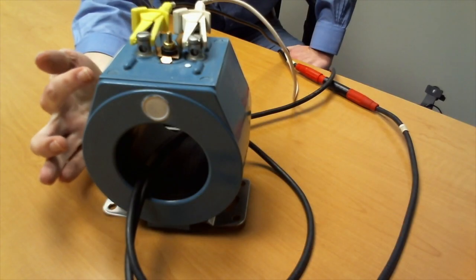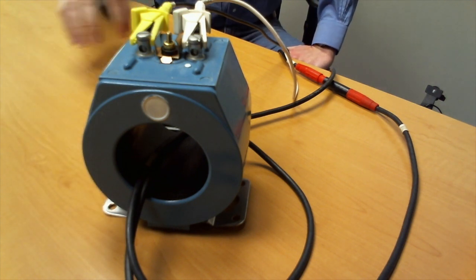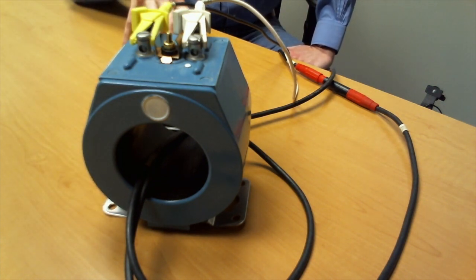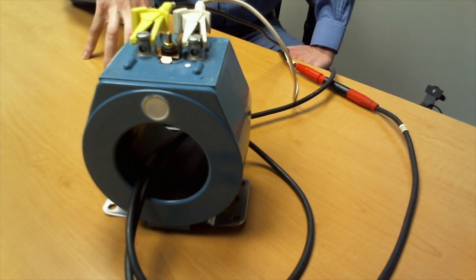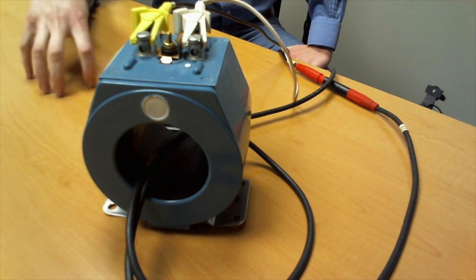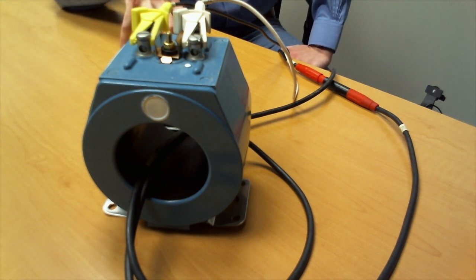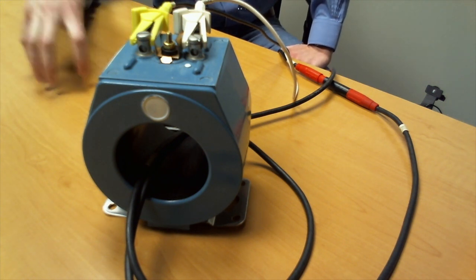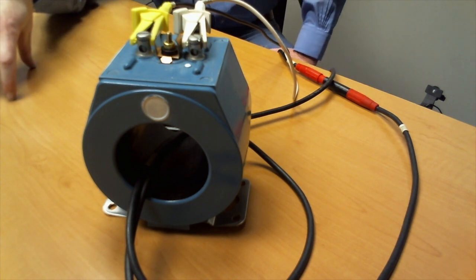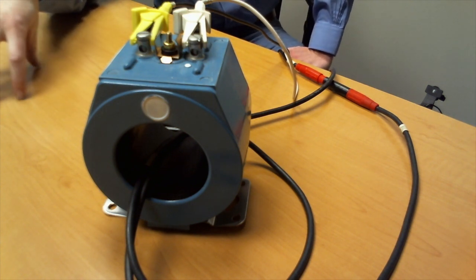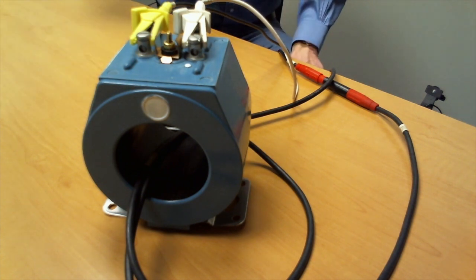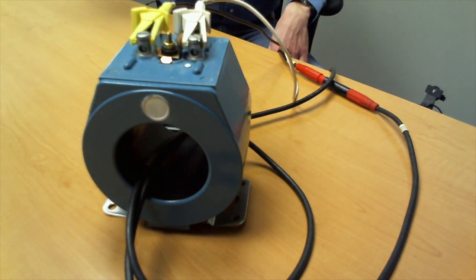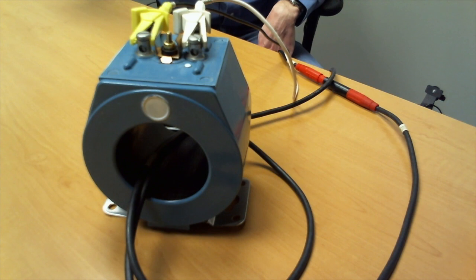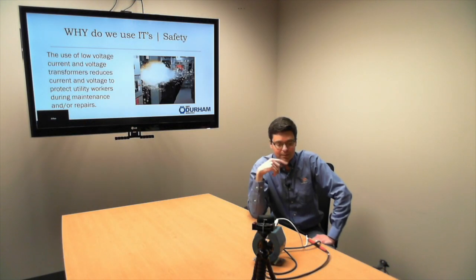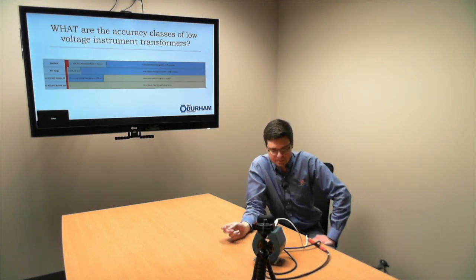But this is a rating factor of 3, which means that if you think about it, it's a 600:5 CT, so at 100% of nameplate, you've got 600 amps. And then if you have a rating factor of 3, you multiply that number times 3. So 600 times 3, 1800 amps is the max current you can hit the CT before it saturates. So it's kind of like this bell curve. The accuracy maintains, but as soon as you hit over 1800 amps, the accuracy goes way down because you go into saturation.